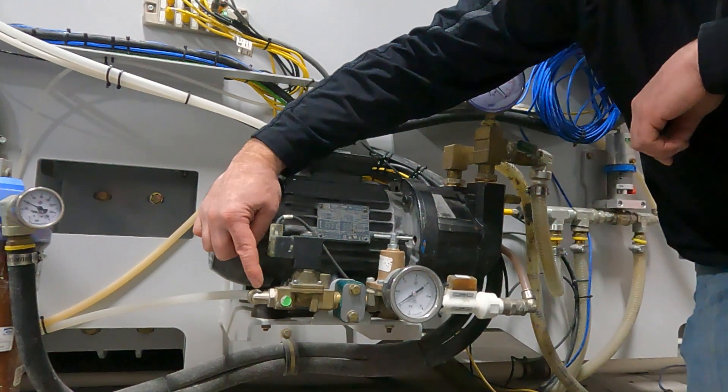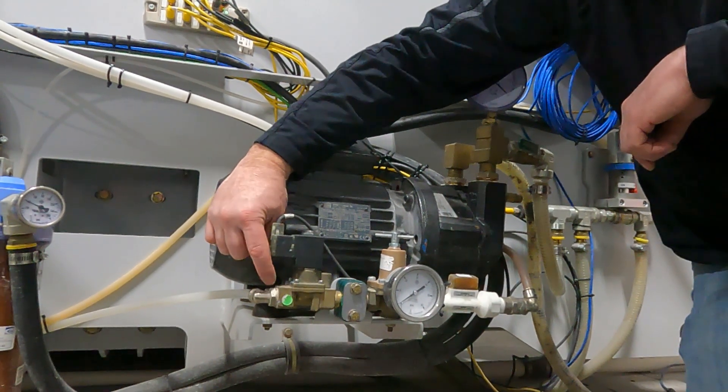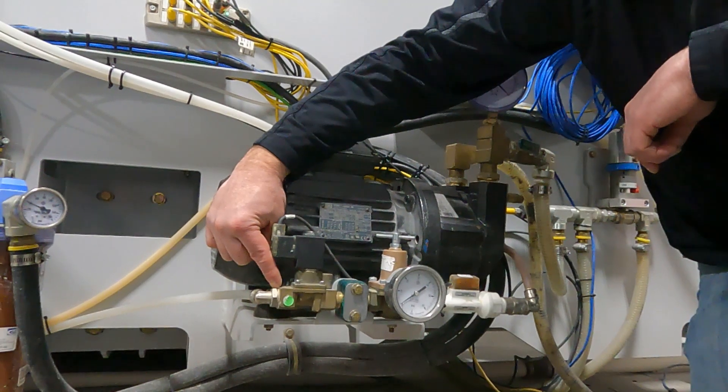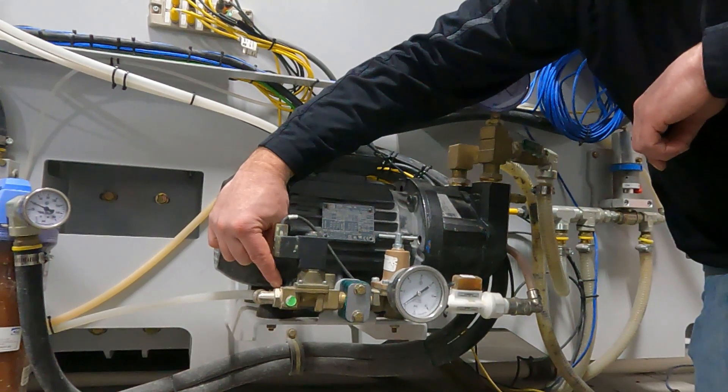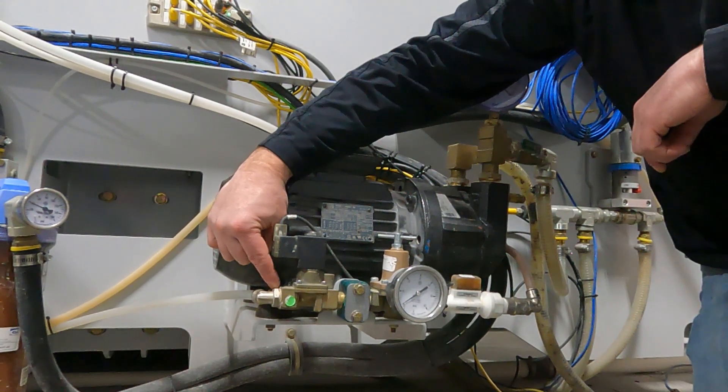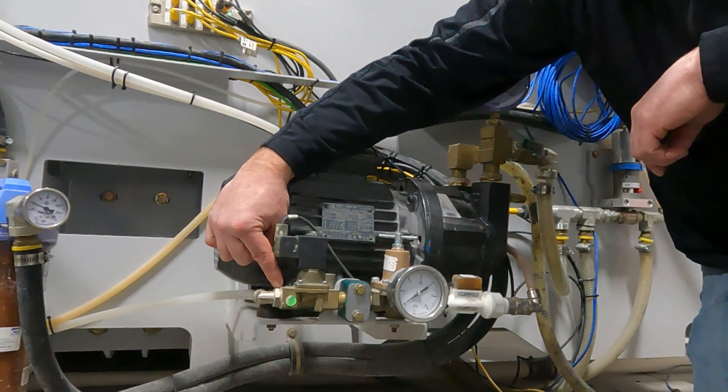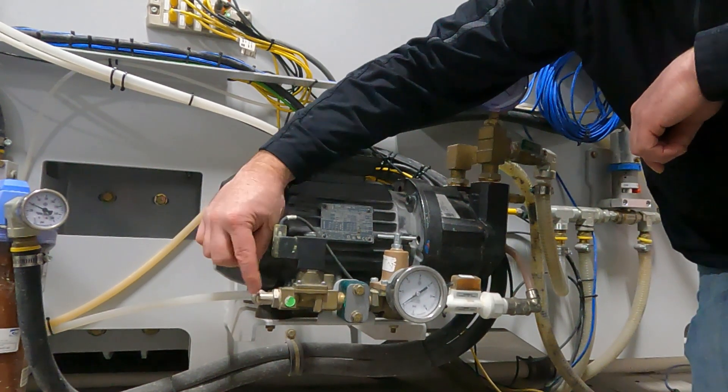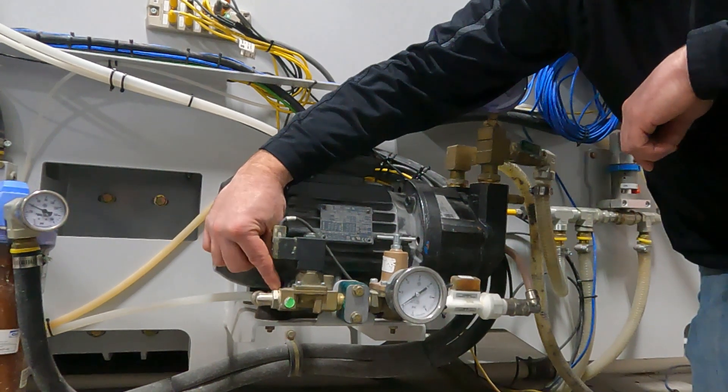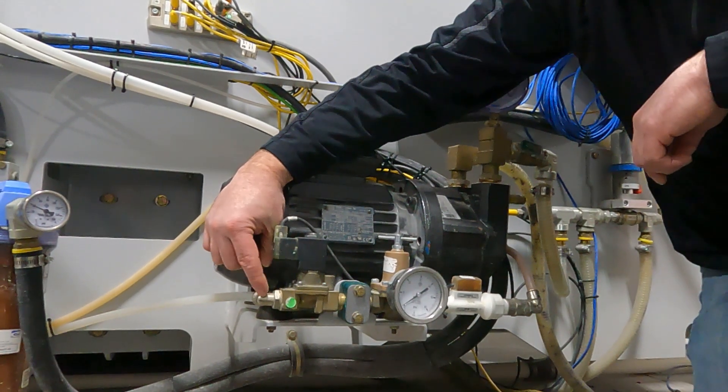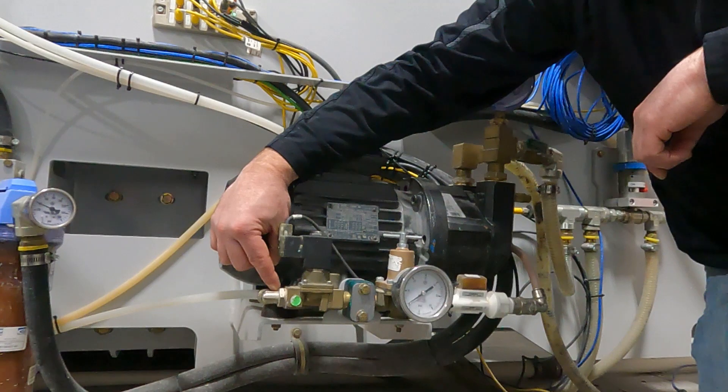Another thing to check is to remove this fitting. And behind there is a screen, an optional screen. You can remove that screen. Park does not require that screen to be in there because of the other filtration going through. So you can remove that or clean if you find that that screen is clogged.